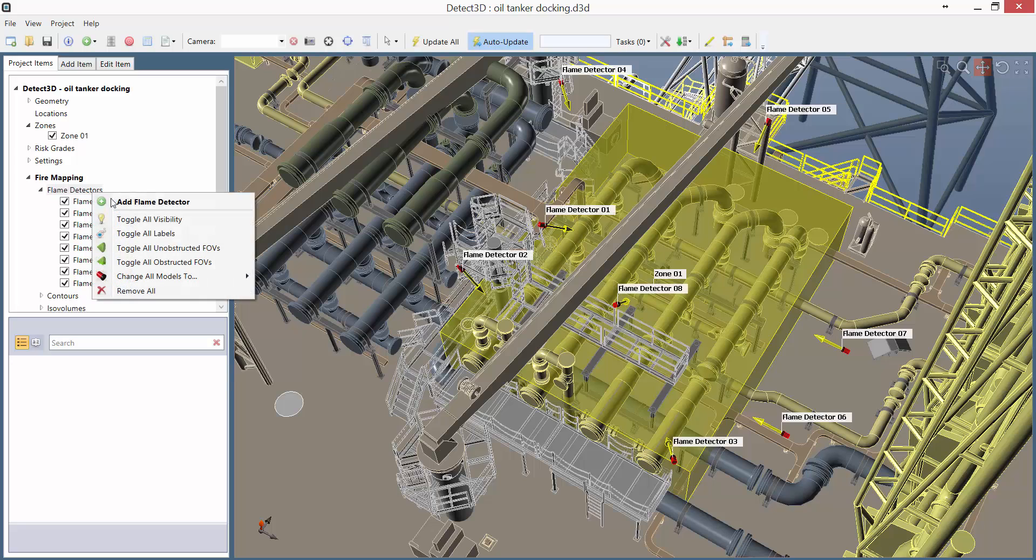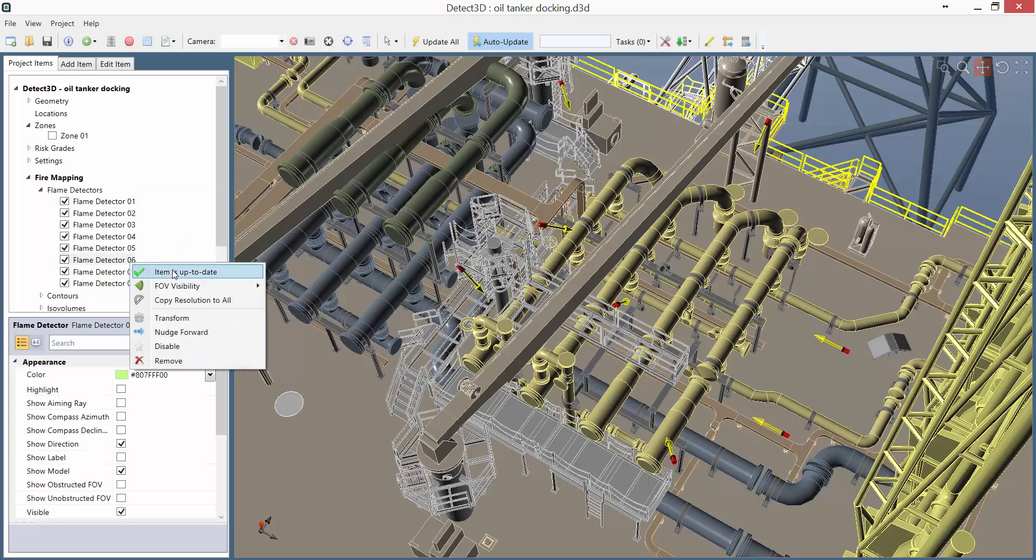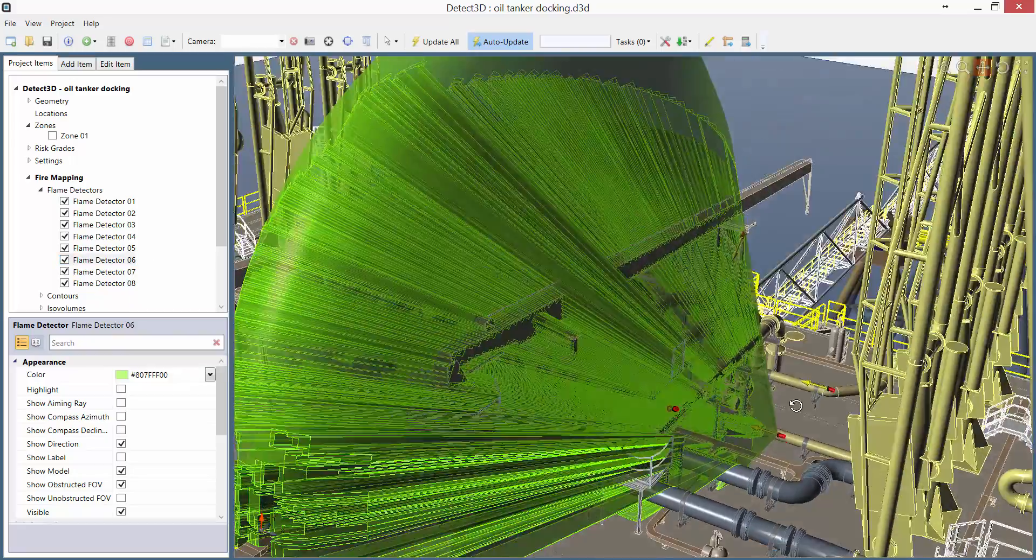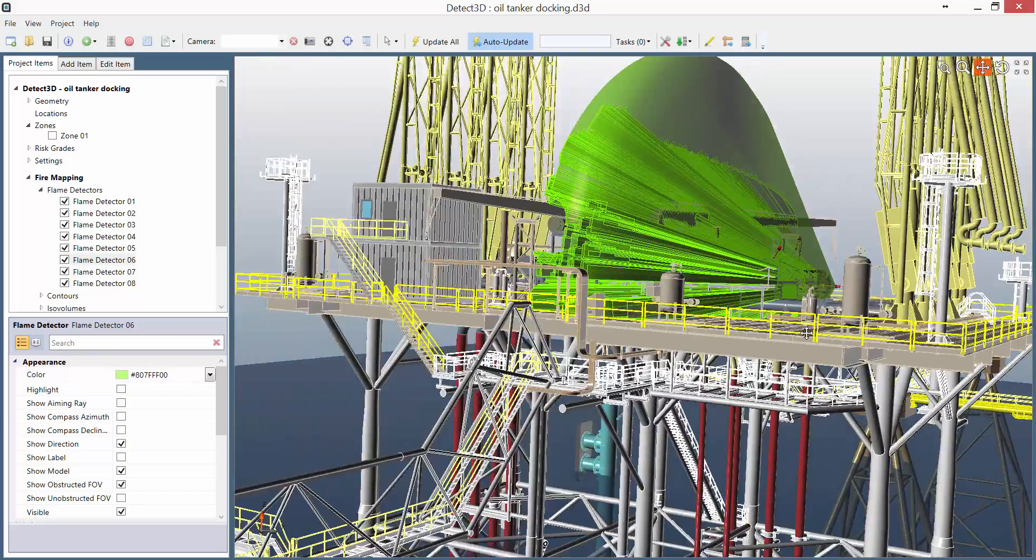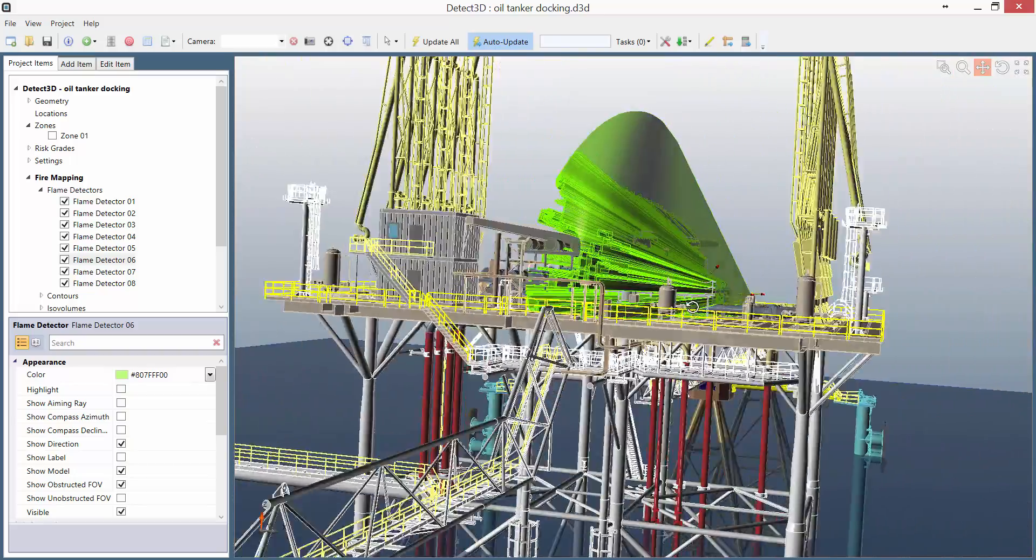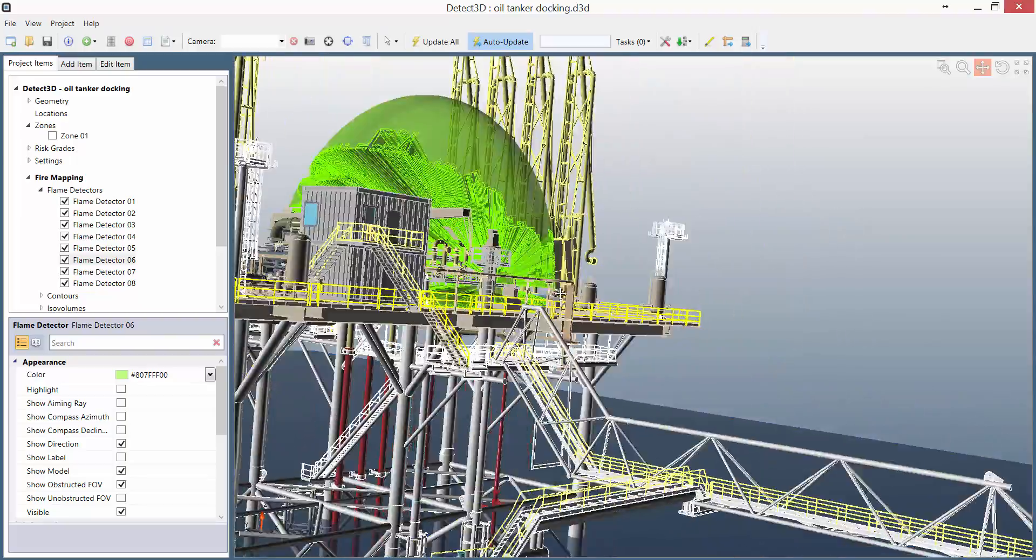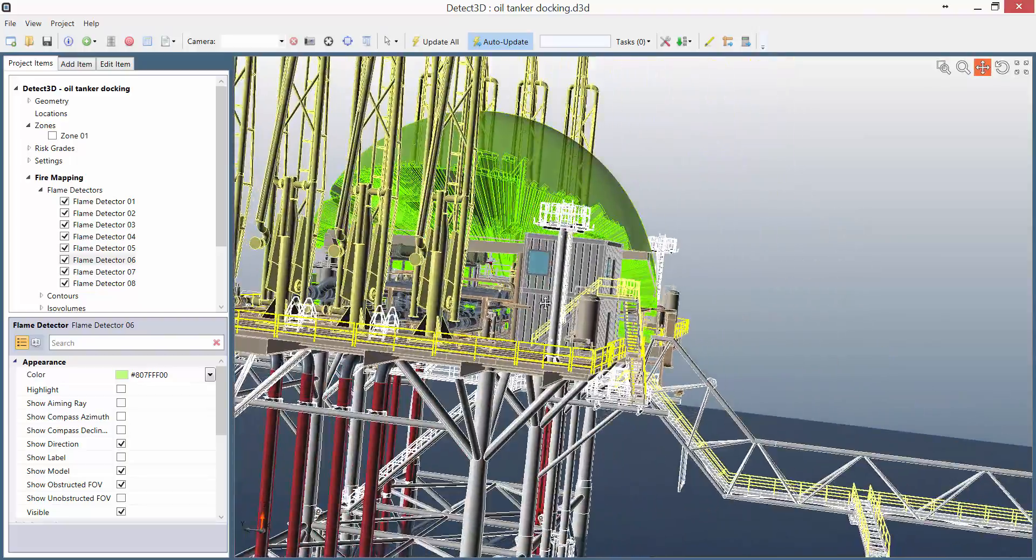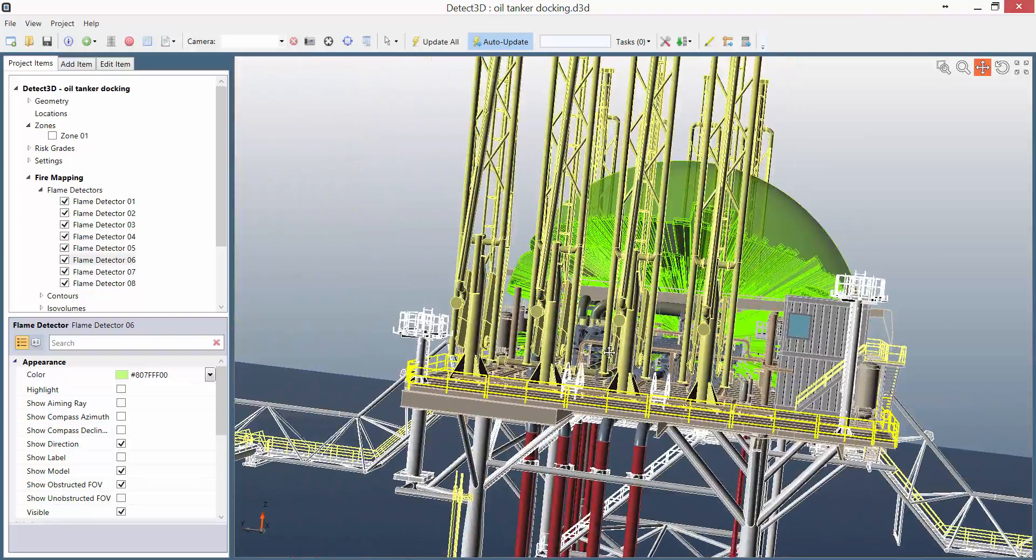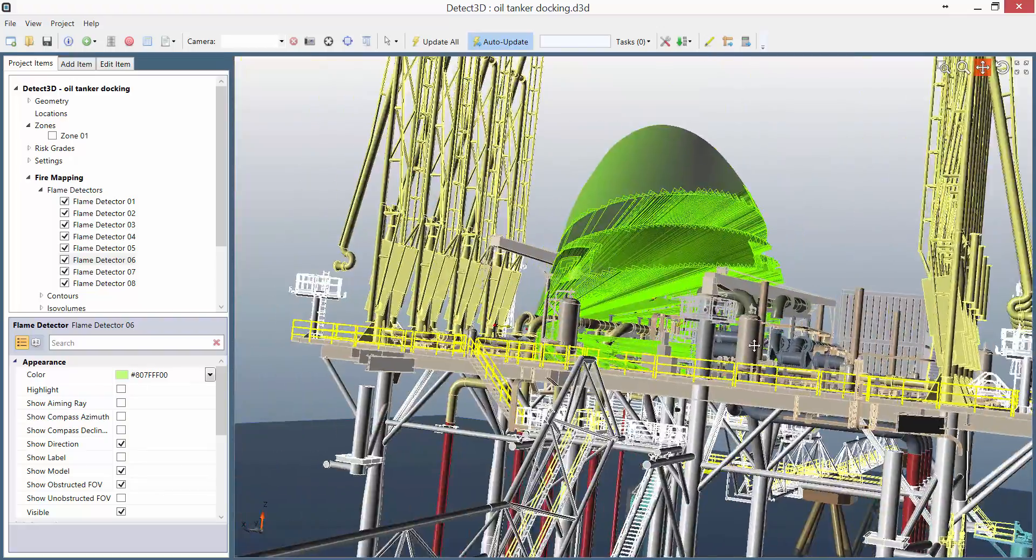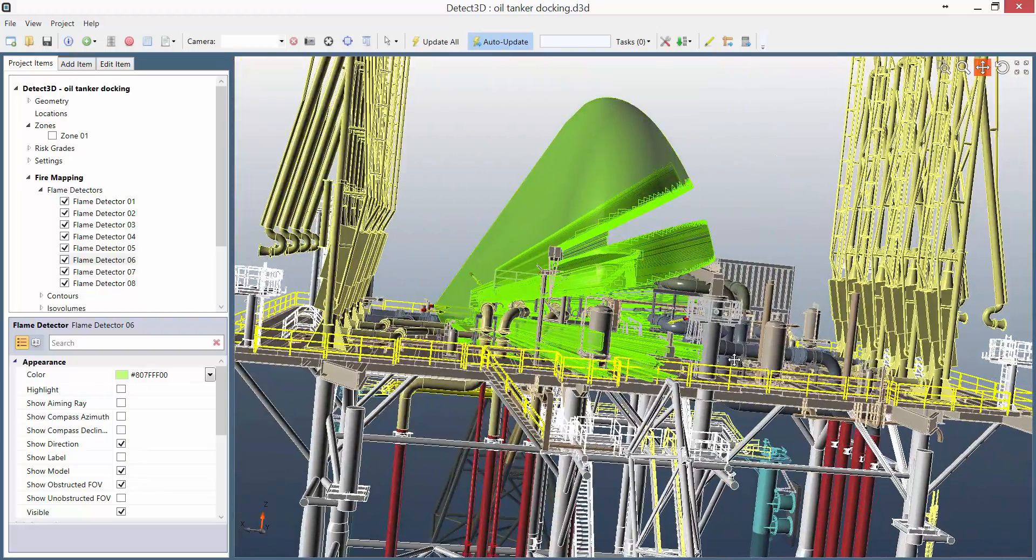For each flame detector we have an obstructed field of view. In a reasonably complex geometry such as this one, the software has had to work pretty hard to calculate the obstructed field of view, casting around 200,000 rays for each detector. For around a million triangle geometry such as this one, it takes around 4 seconds to calculate on a standard laptop.